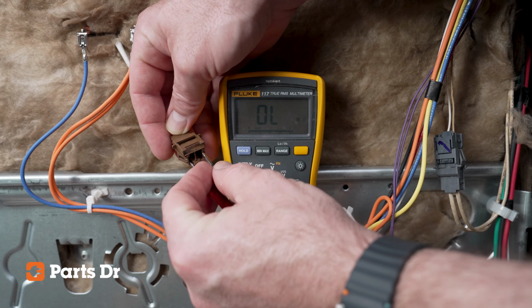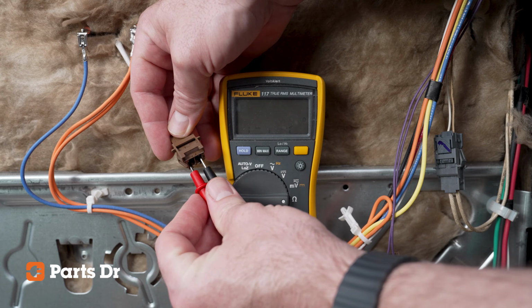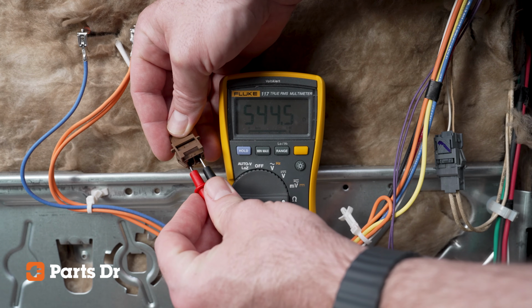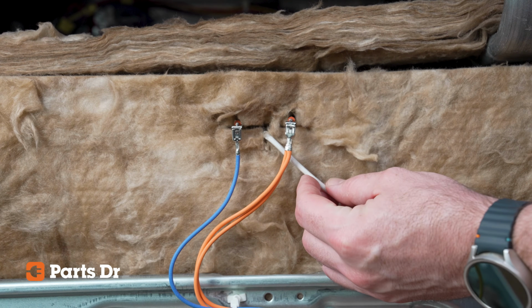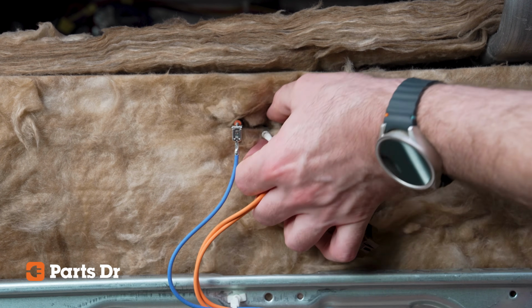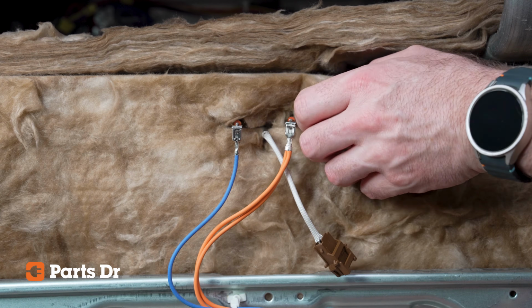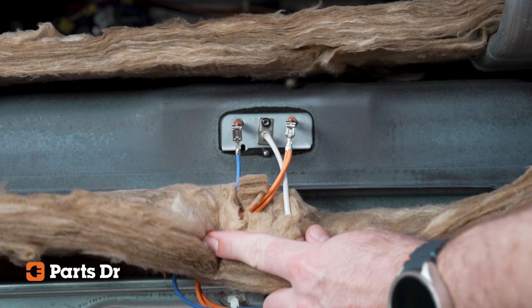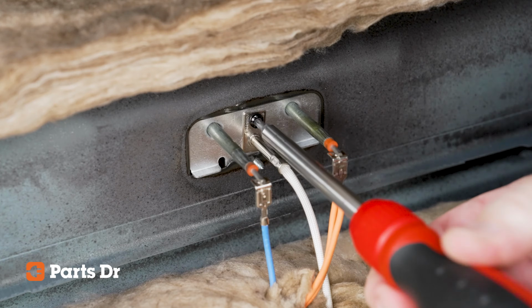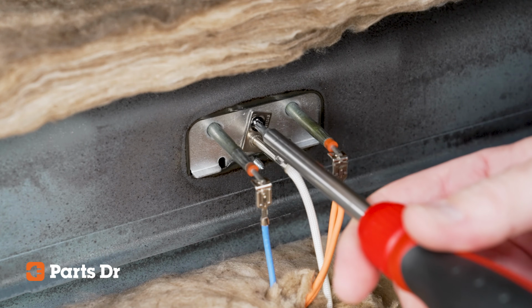For more information on how temperature sensors work and how to test at different temperatures, please watch our temperature sensor testing video. To remove the sensor, trace the wires into the back of the oven wall and move the insulation away to expose the single T20 Torx mounting screw. Remove the screw and pull the sensor from the oven cabinet.